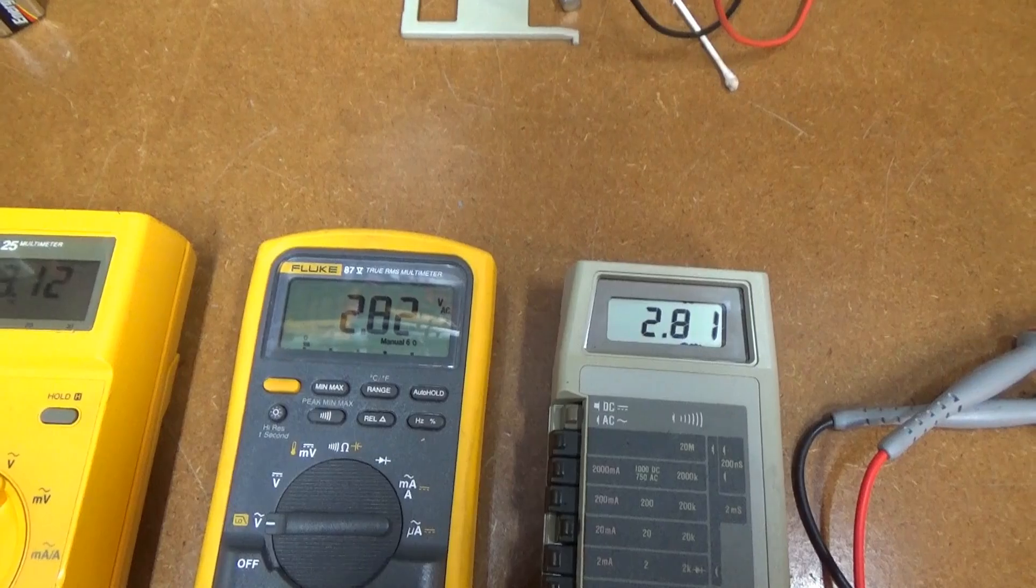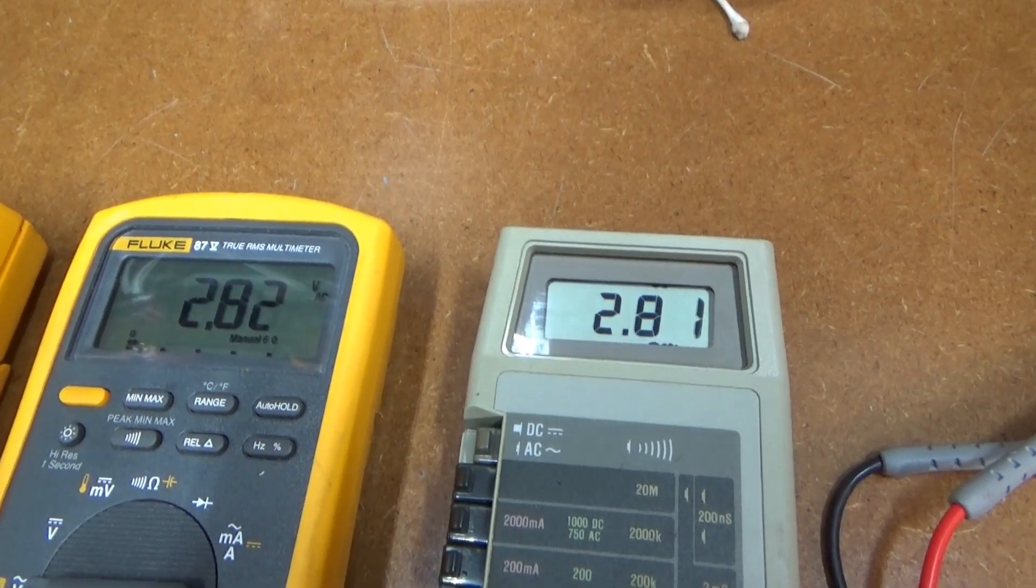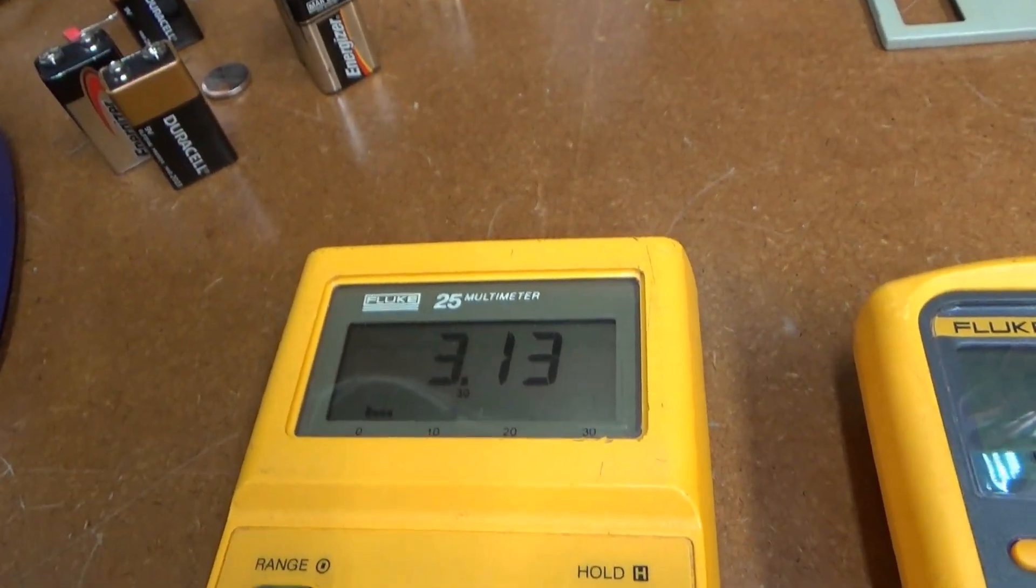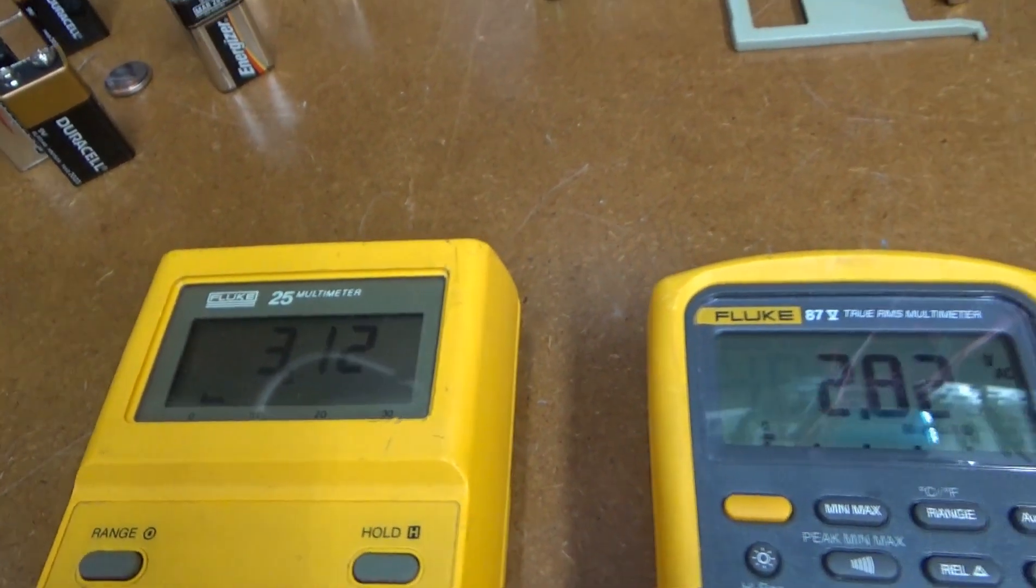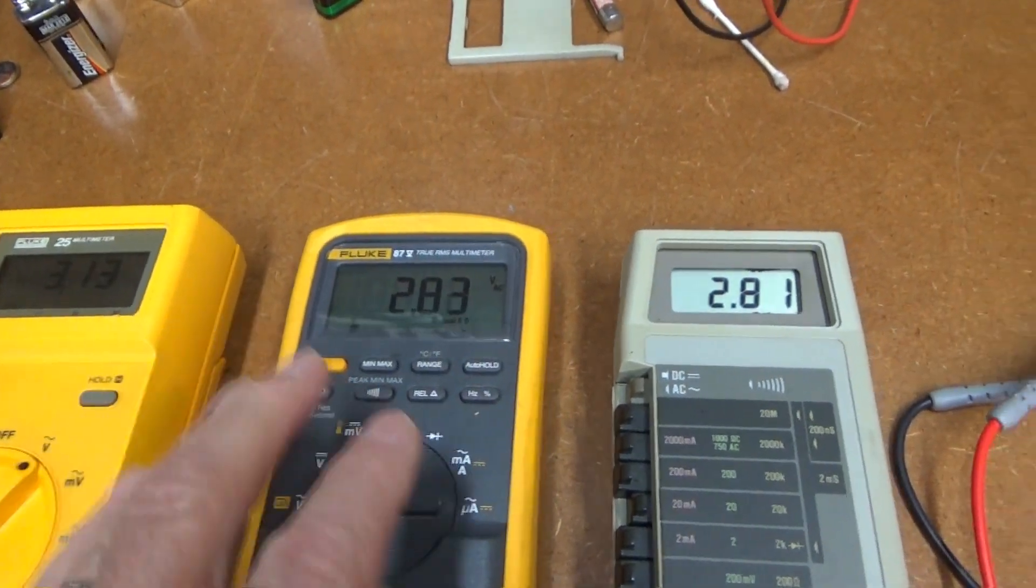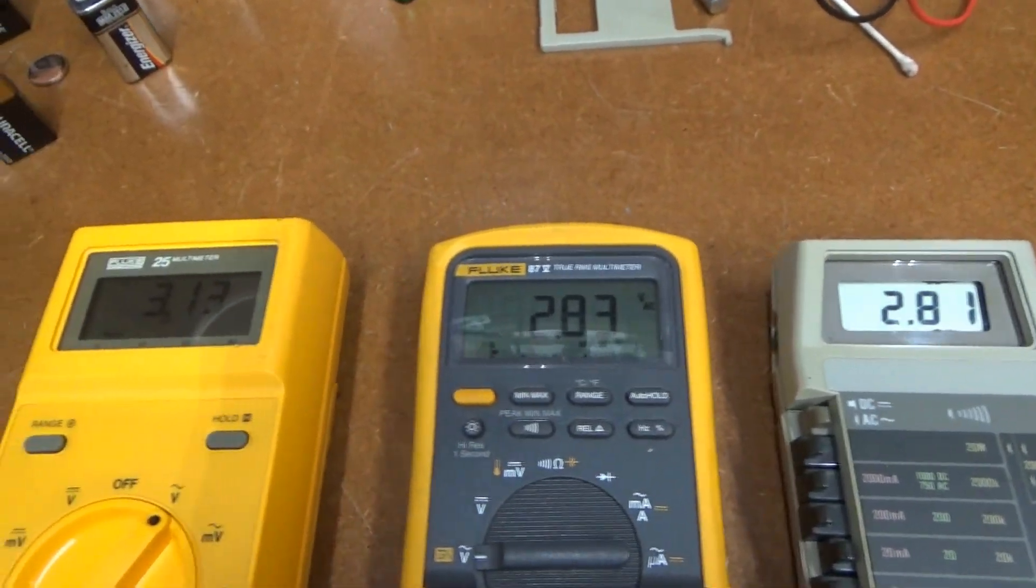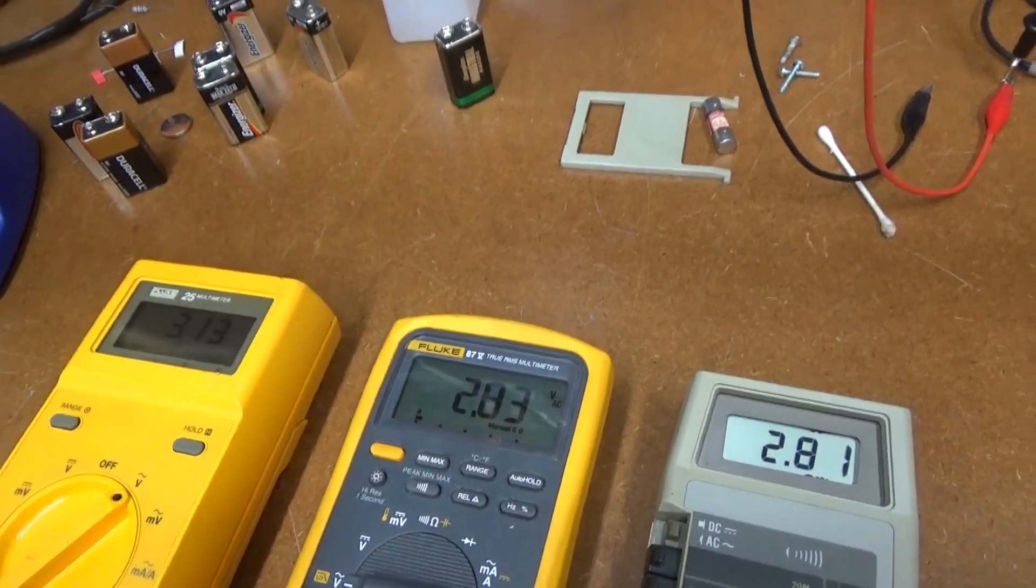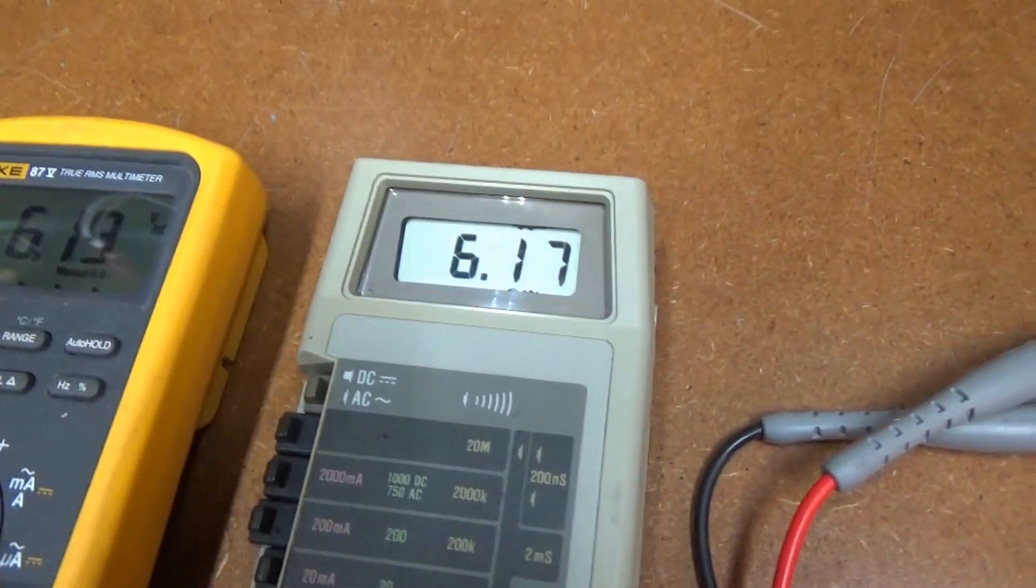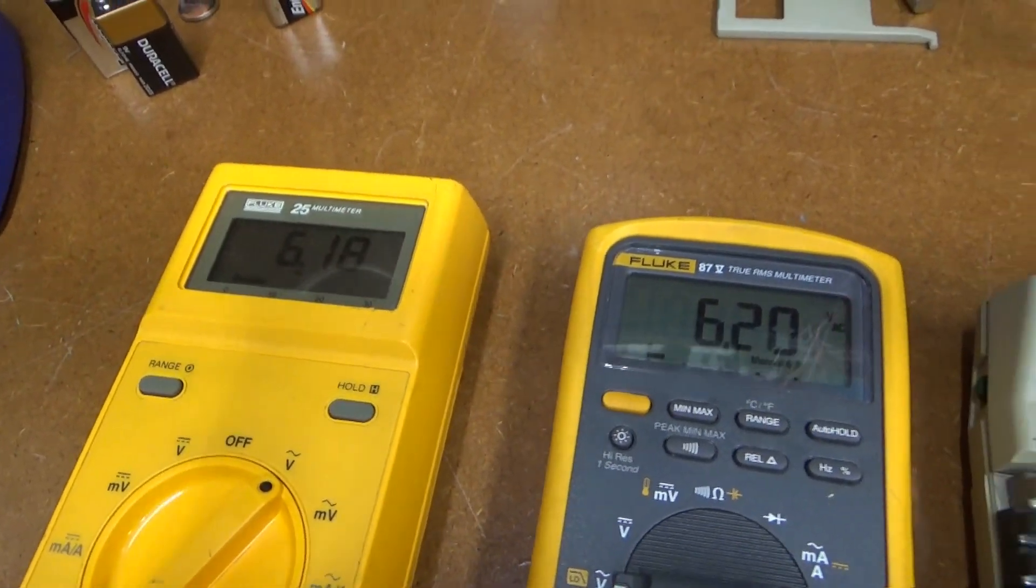Now watch what happens when I switch to a square wave on these. They all drop down just because of the source. But you see the two True RMS meters are reading about the same, 2.81, 2.82. But the average responding meter, this old Fluke 25, is measuring 3.12, which is how these things work. Average responding will read higher than a True RMS meter on a square wave. It will vary depending on what type of wave you have. But on sine waves, it will read pretty much the same.